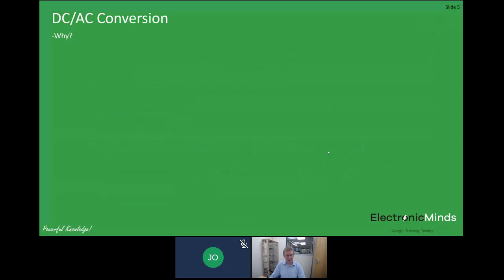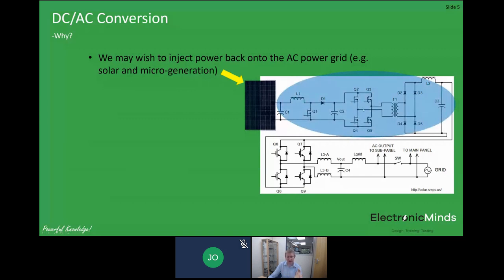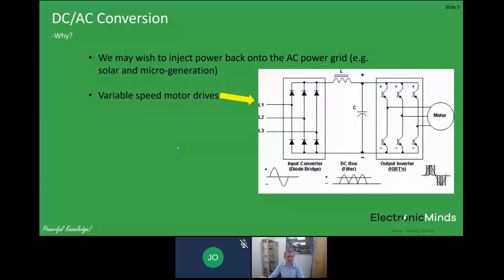DC to AC conversion — why do we want to go back again? There are many reasons. If we've got some micro-generation — say a solar farm — we're generating power natively in DC. If we're going to feed that back onto the grid we need to turn that back into AC. In those solar farms we have a DC to AC conversion block. In this example the first part is an isolated DC to DC converter to step up the output voltage from the solar panels to a high voltage DC link and implement maximum power point tracking. That high voltage DC link then feeds a second stage inverter, which turns it back into an AC waveform that can be synchronized and fed back out to the grid.